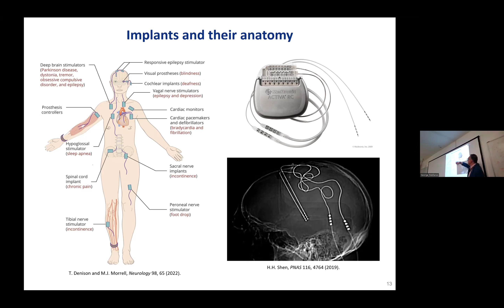Now, the front for research and for development is where electronic materials come in contact with tissue. That is the single most challenging bit of the device. And in all of these devices, it looks pretty much the same. So you have electrodes that are quite macroscopic, millimeter size. They're made out of platinum with a little bit of iridium to adjust mechanical properties. And they're encapsulated in an insulating matrix, typically a polyurethane or a silicone.